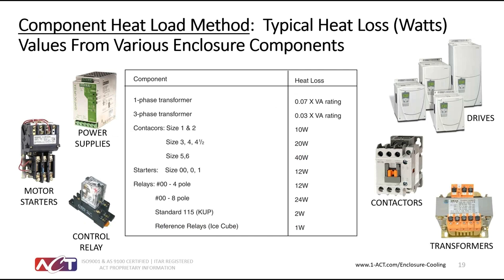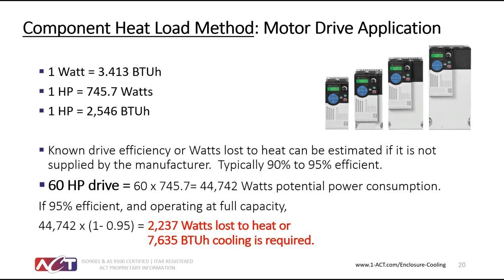Or you could do a component type calculation where you would look at power supplies, motor starters, or PLCs, or whatever goes into the cabinet, and figure out what each of those devices would add to heat load as they're functioning or operating. And then finally, a very common application that we run into with our heat exchangers is cooling drive cabinets. If you ever wanted to figure out what the load of a drive is, you could convert the horsepower to watts, and then you take the efficiency of the drive, which is typically 95%. So in this case, a 60 horsepower drive would produce about 2,200 watts of heat load, or if you converted that, it's basically 3.413 times the watts to get BTUs, so you'd get about 7,600 BTUs of cooling required. We do have a calculation tool that we'll show you later on how to select these products, and you can work in either watts or BTU as your heat load variable.